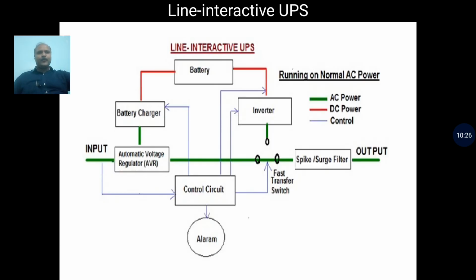Line interactive UPS. This is also one type of offline operation, but it provides reliable output. As the name implies, line interactive, it is an uninterrupted power supply whose function is according to the line. A line interactive UPS conditions and regulates the AC power from its utility. It consists of a passive filter as well as a tap changing transformer. It may consist of an automatic voltage regulator as well as spike and surge filters.